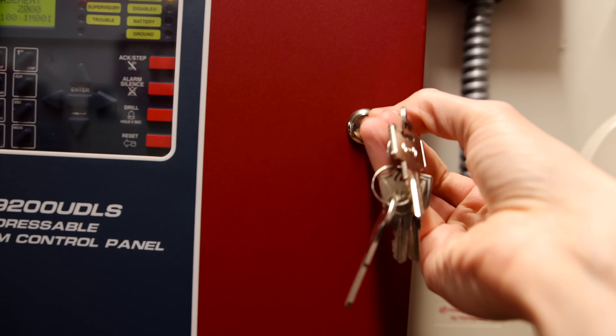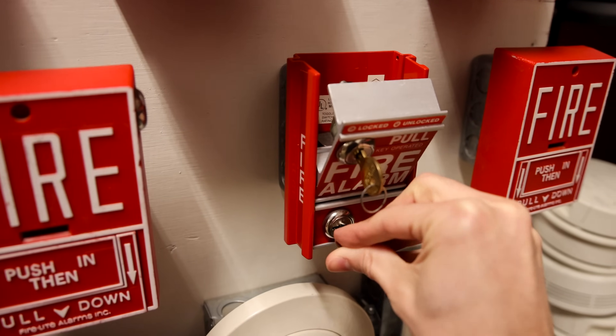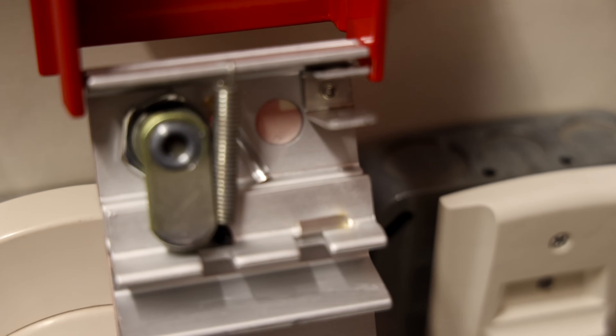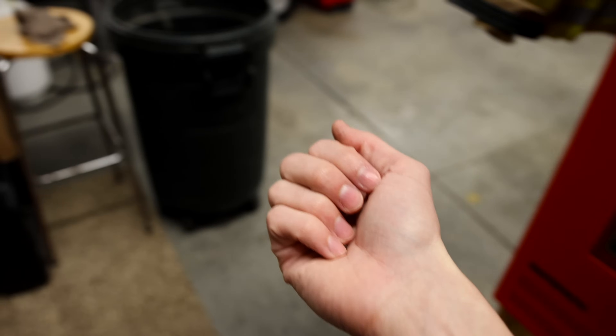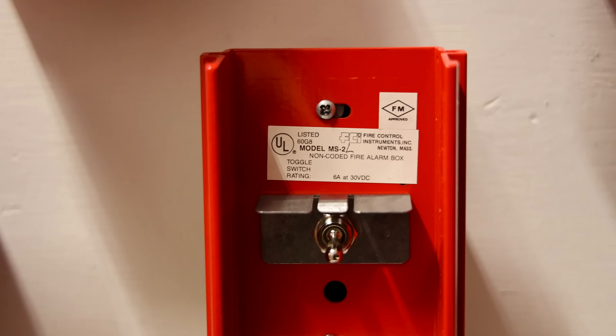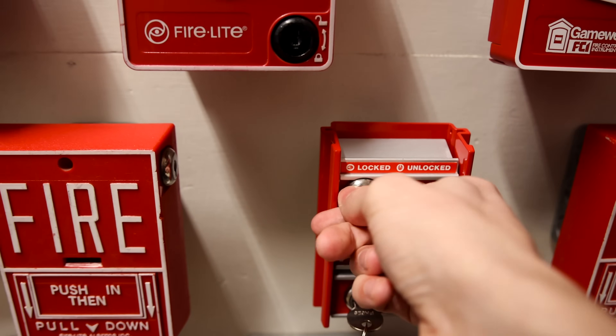Let's reset the MS-2L — we'll need the FCI key. There might be some glass; it definitely looks like the break rod is gone. It broke into two pieces — actually a nice clean break, so no need to clean up a thousand pieces. You can see on the inside it says MS-2L, non-coded fire alarm box. We'll close up the pull station; the switch has already flipped back down, so we don't have to worry about that.